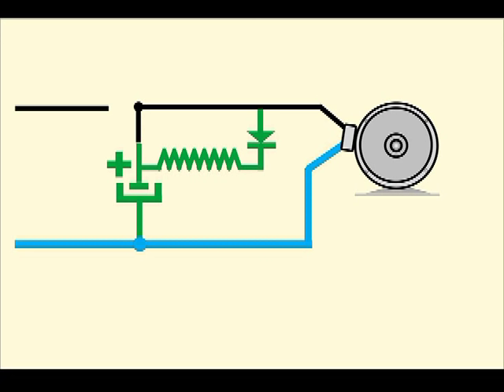In an induction motor that has just been switched off and is rotating by inertia, it is enough to apply a small direct current pulse to the stator windings so that the motor acts as a generator for a second or longer, inducing an intense current inside the rotor, whereby the squirrel cage rotor is inductively blocked, stopping the motor almost immediately.